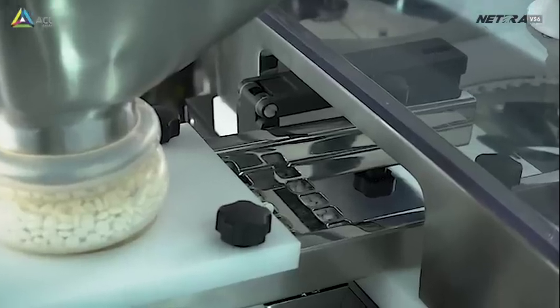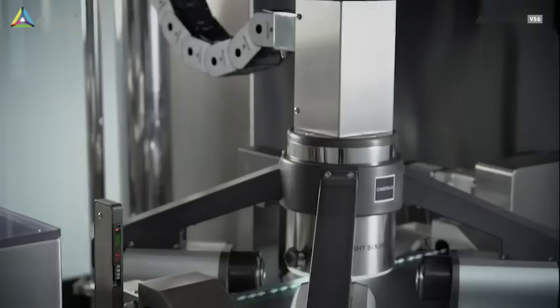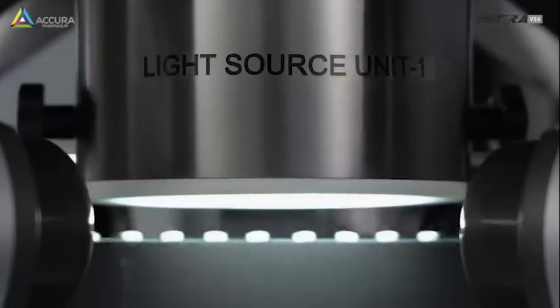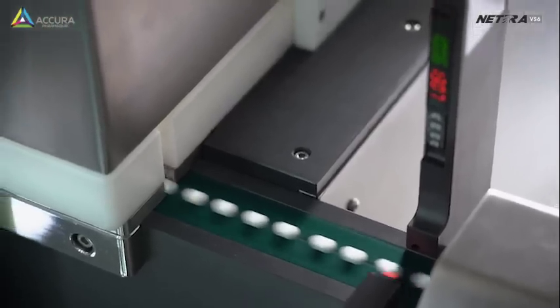NETRA VS6 inspects each tablet with high-speed, high-resolution industrial cameras — 4 from the sides and 2 from top and bottom. Each camera has its own image processing control that captures, processes and feeds the result to the PLC and the main computer in milliseconds.